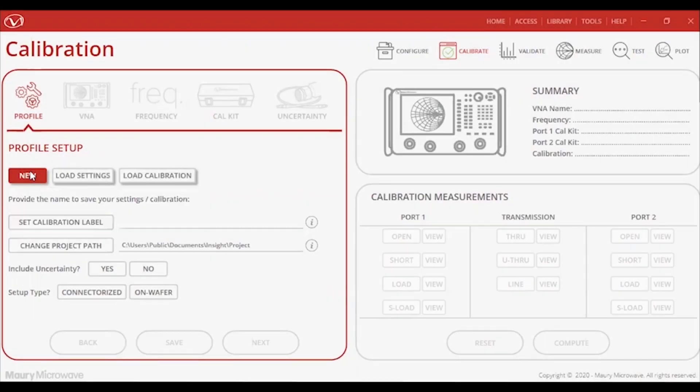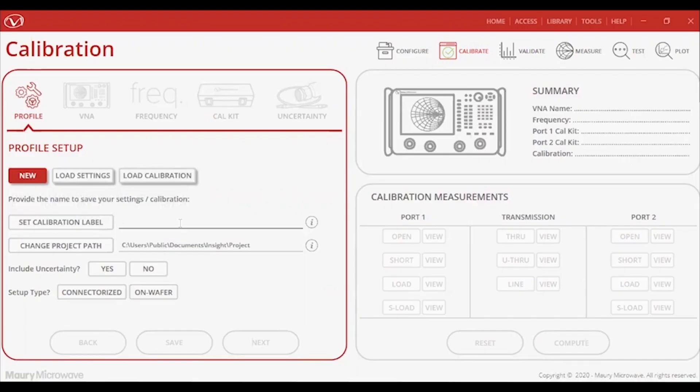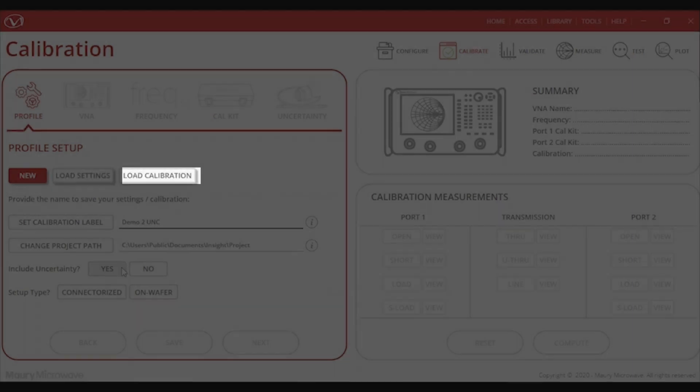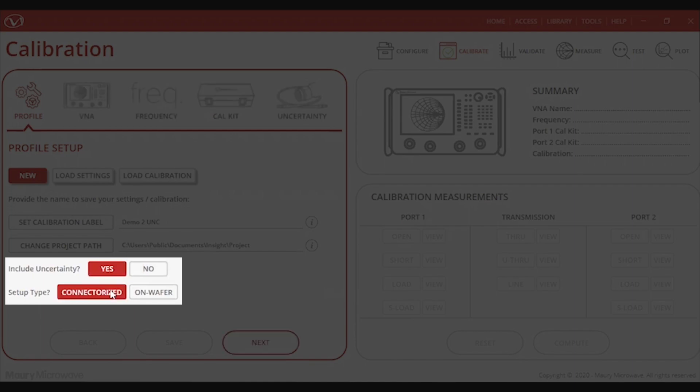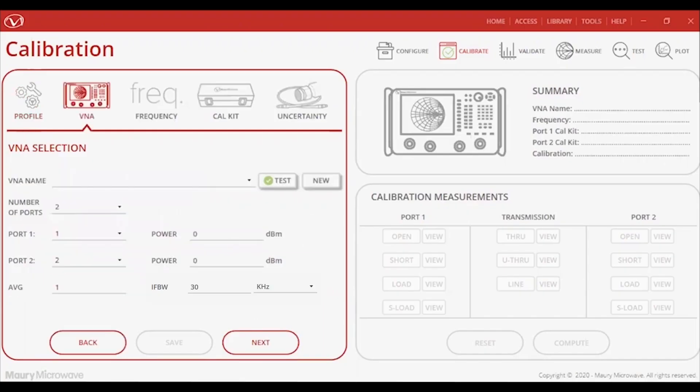Now that all the tabs inside the Configuration and Settings module are covered, let's move on to the Calibrate, Validate, and Measure module. First, let's take a look at the Profile Setup tab where the user can either create a new calibration profile, load an existing profile, or load an existing calibration. This can be very helpful to replicate identical setups regardless of the person driving the software. You can also choose whether to include uncertainties and if your measurements will be coaxial or on wafer.